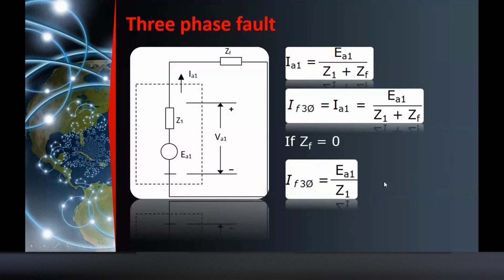For a three-phase fault, per unit, this is all you need to remember, and I will give a derivation later. But if you are already practicing, just remember this: I fault 3-phase per unit is simply V, or EA1, divided by Z1. Only the positive sequence network. Okay?